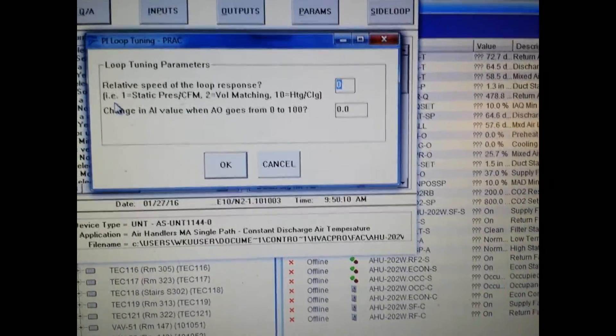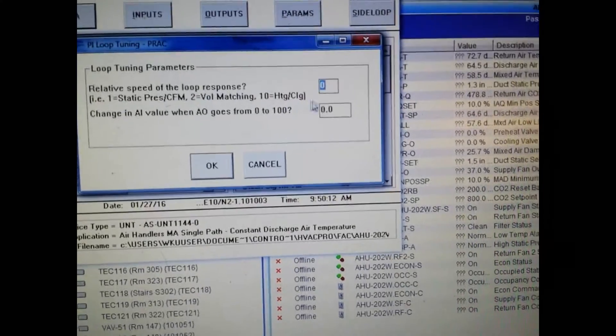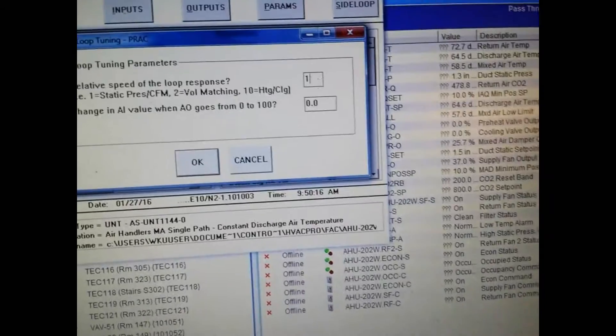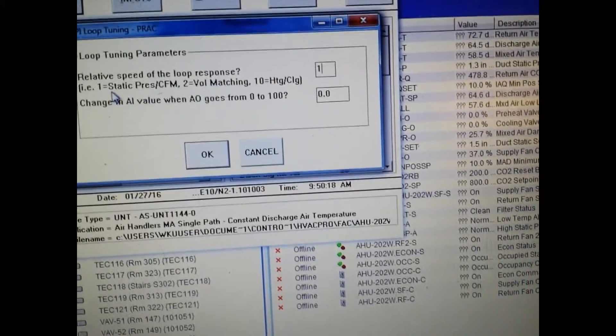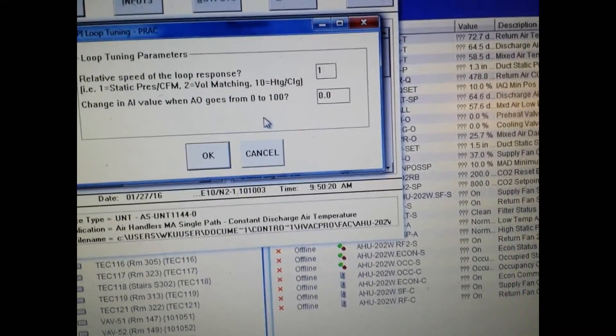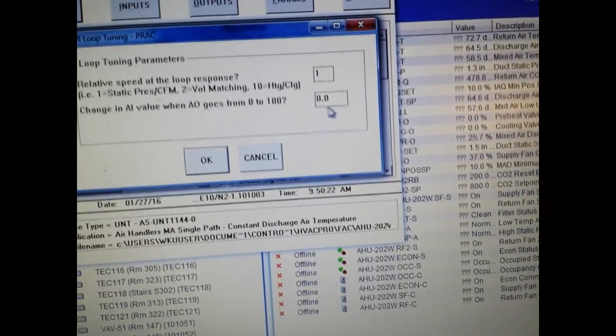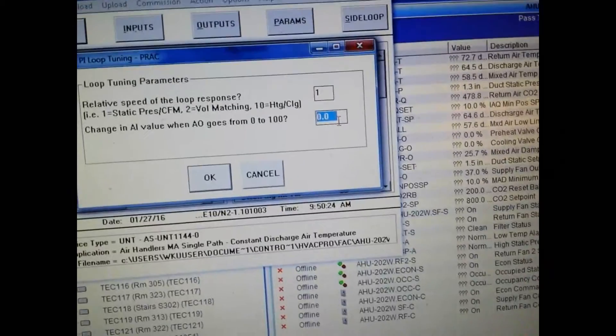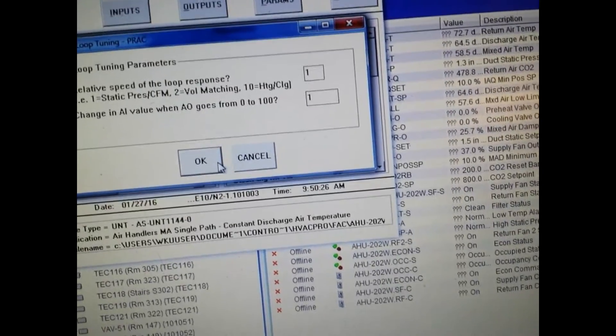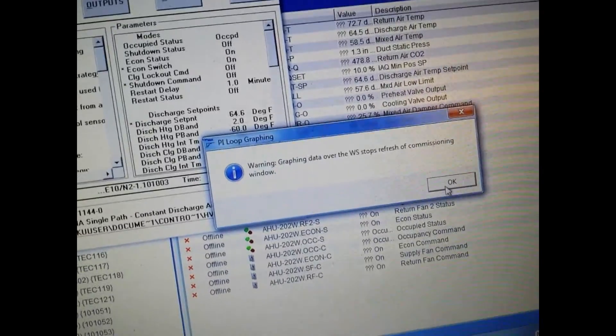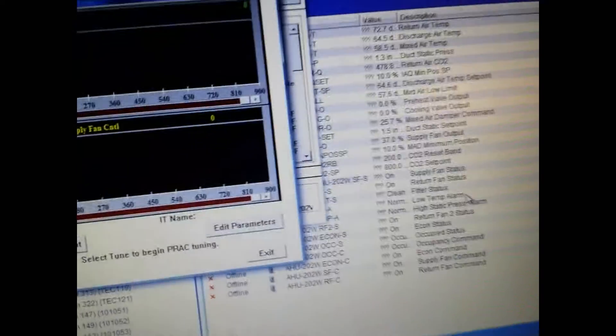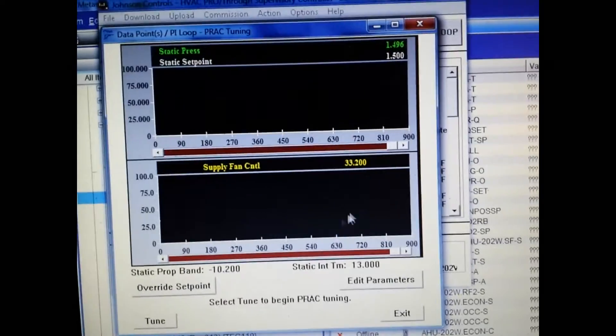You're going to come into this window here. And since we are going to be tuning the static pressure we need to change this value in this box to a 1. You can see the little indicator here that tells you the value for the particular loop that you're tuning. We're also going to change the second one to a 1 as well. Now this little warning button - and we click the OK.